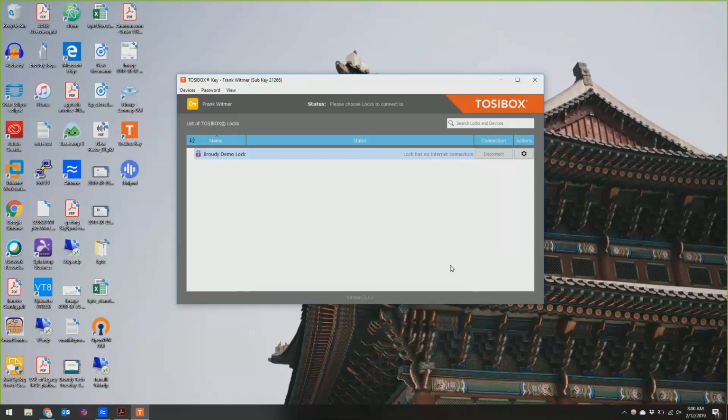So like one of the hierarchies that I built for the demo is to break out all the controllers that are installed by manufacturer. And the way that I'm doing that is I've made my own tag called manufacturer, and it's a string, and I'm just putting in Honeywell, JCI, the name of the manufacturer in that tag, and then my hierarchy is grouping them based on that tag. So all of the things that are tagged JCI are getting put in a folder, and so on and so on.